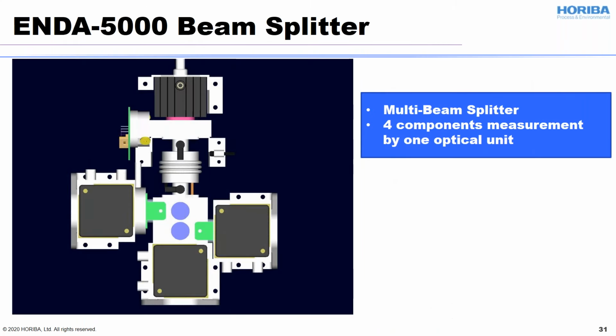HORIBA designed the detectors with a beam splitter, and the light source travels like this. Each split light reaches each detector. So the one optical unit makes a 4-parameter analysis. Here is a CO2 measurement detector, and NOx, SO2, and CO, things like that. Just one optical unit makes a 4-parameter analysis, which is great. And this reduces the number of parts and realizes better performance.